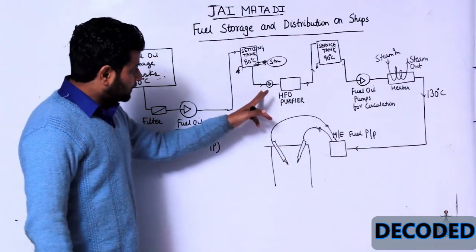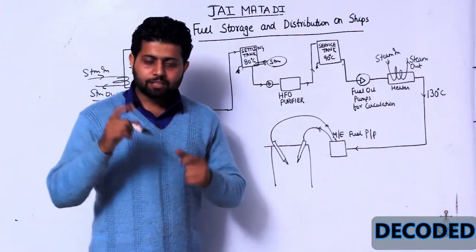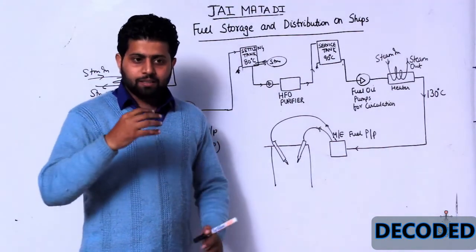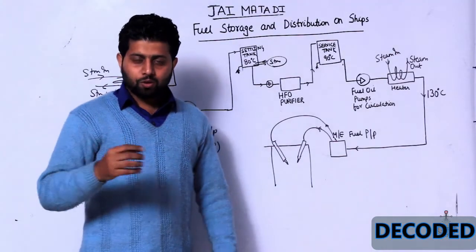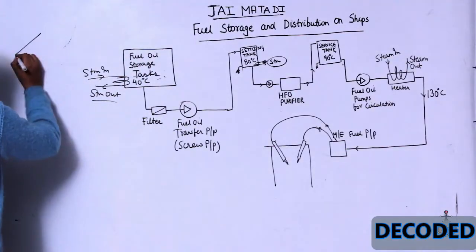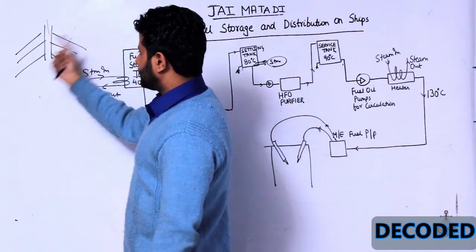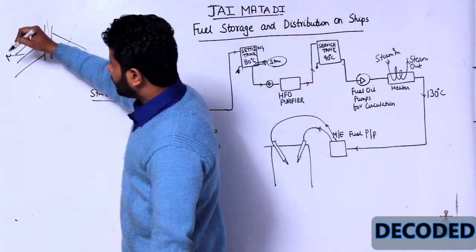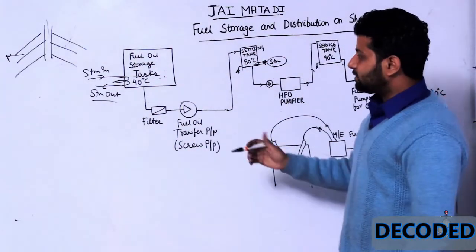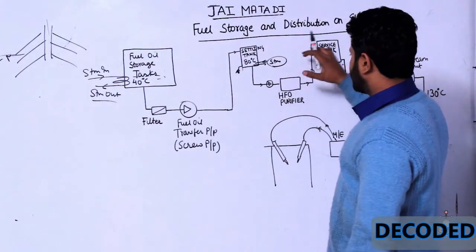After settling, the oil goes through a heavy fuel oil purifier pump into the purifier. The purifier works on the principle of centrifugal force, rotating at a very high RPM — up to 9000 RPM. Different density objects experience different centrifugal force. Water molecules are heavier so they move out, while oil stays in. Any sediments or hard molecules also move out due to higher density, and the clean oil goes into the service tank.